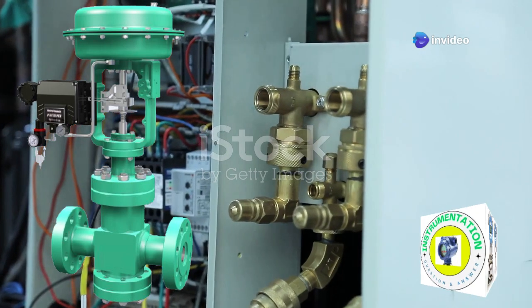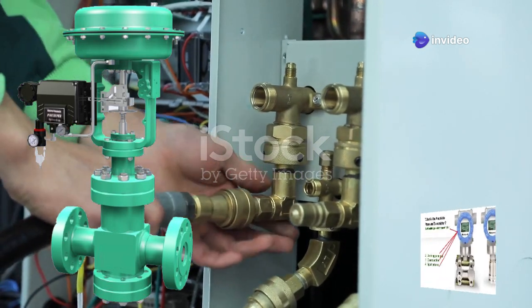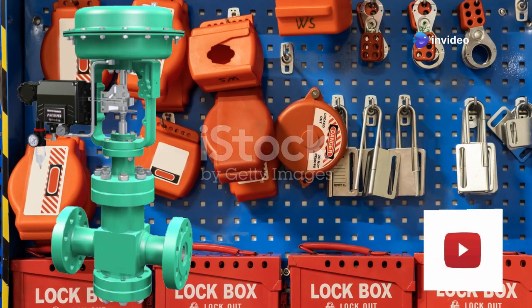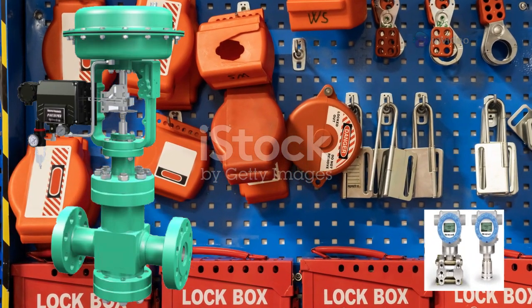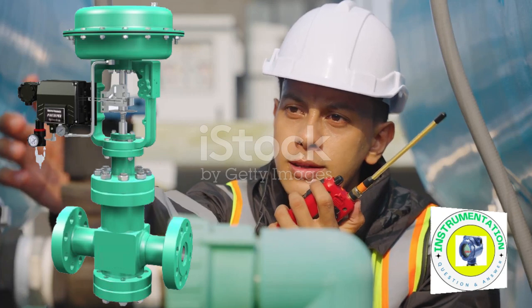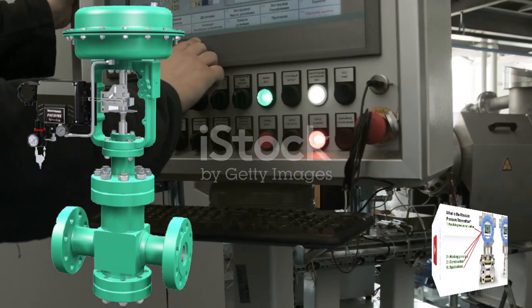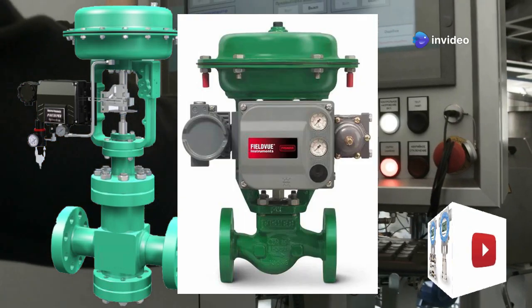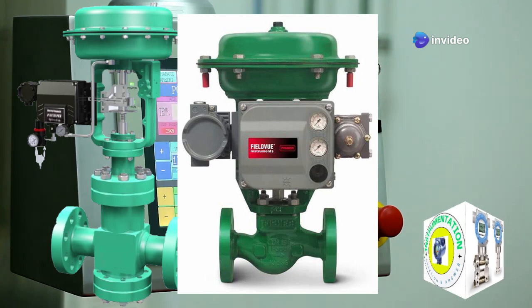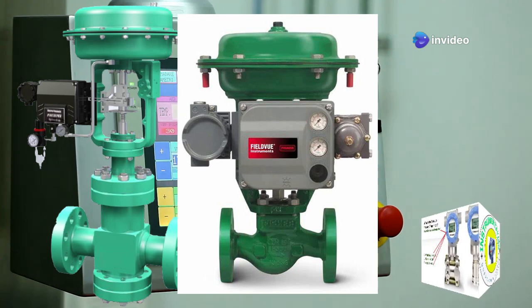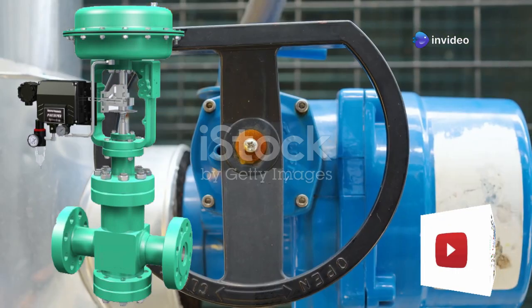Alright, let's jump right into auto-calibrating your smart valve positioner. First things first, make sure you've handled your lockout, tagout, and confirmed the valve is safe to work on. Safety's not optional. Now, head over to the positioner and enter the Setup or Configuration menu. Usually, you'll find an option called Auto Calibration or something similar. Select that. The magic starts here.